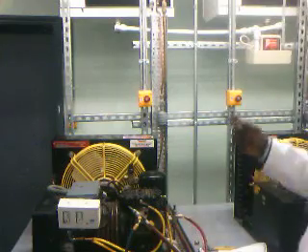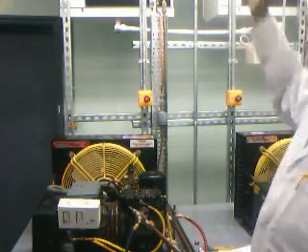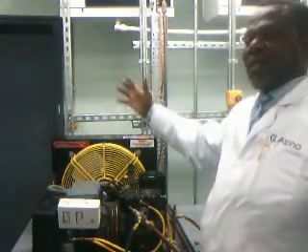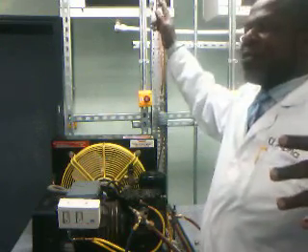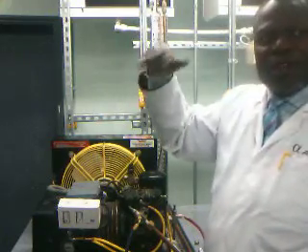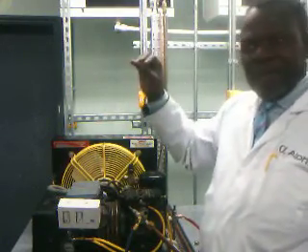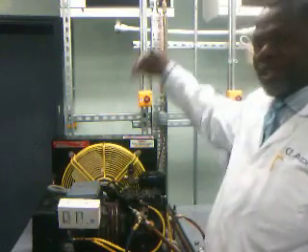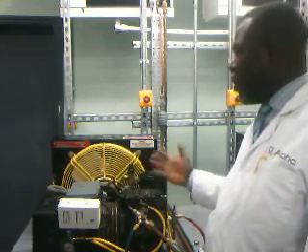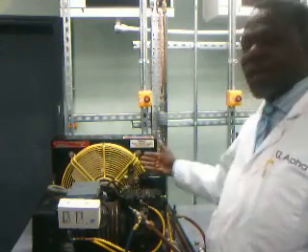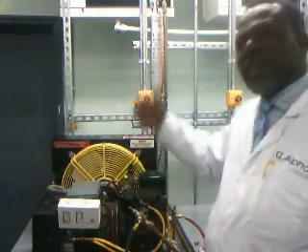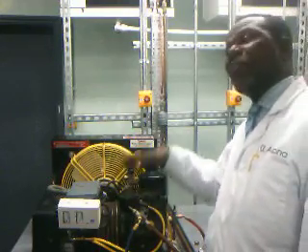Now, if you over-condense and you don't check it, you end up with refrigerant going into the evaporator. It will absorb all the heat, but it will still have a bigger capacity to absorb more heat. That means all your refrigerant will not boil off. Maybe 80% of it evaporates and 20% will remain liquid. That liquid will spill over into the suction, mix with the suction gas, and enter the compressor and affect it. Of course, if you have an accumulator on the suction line, it can stop the liquid entering the compressor, but that doesn't mean that we should deliberately create that problem.